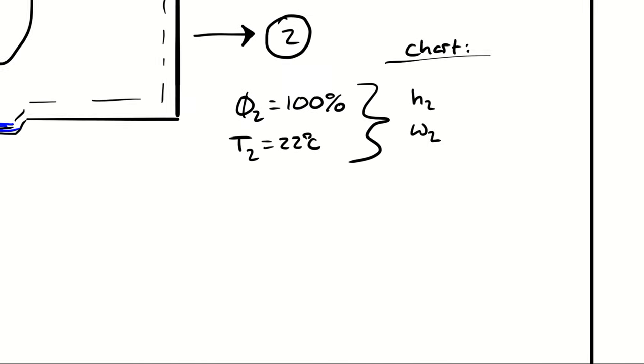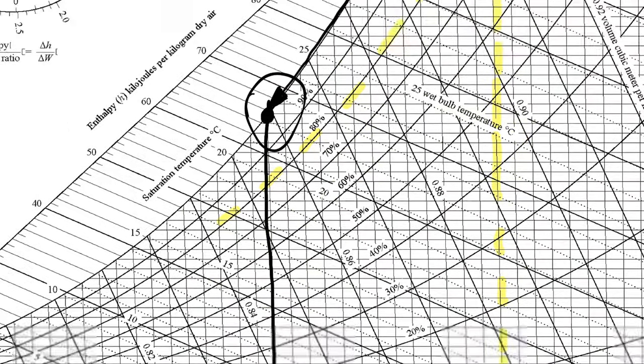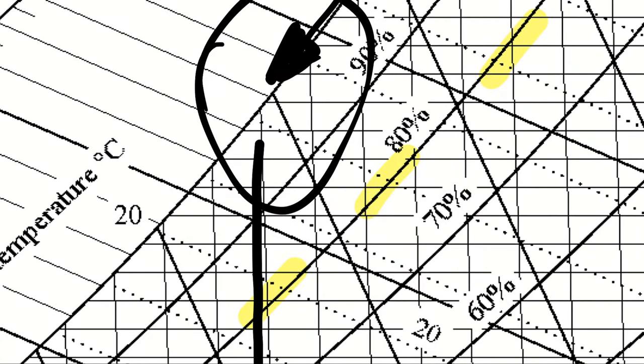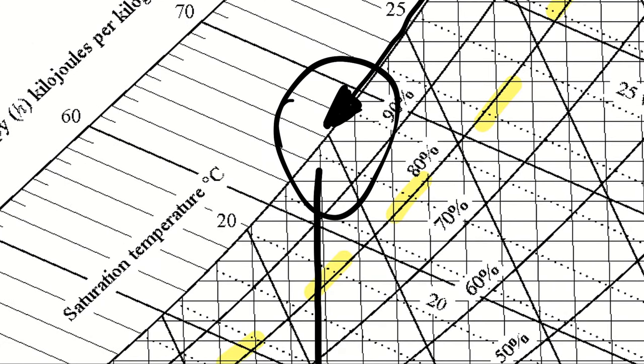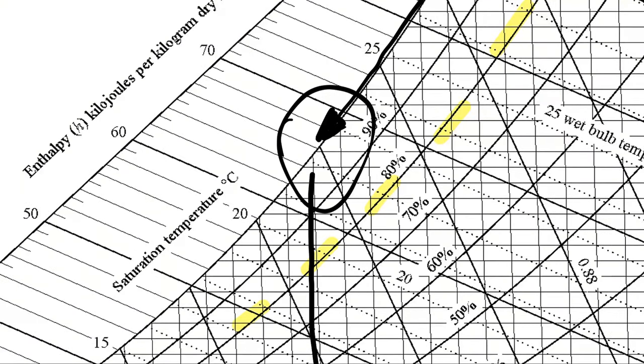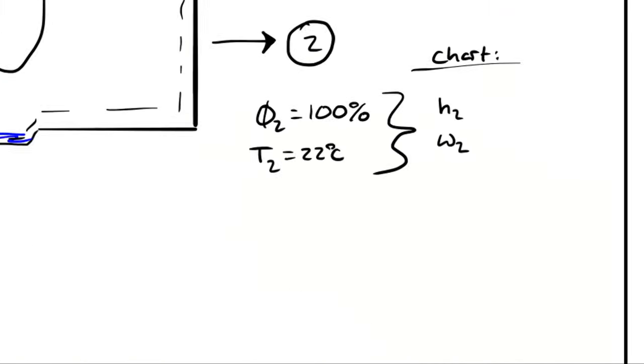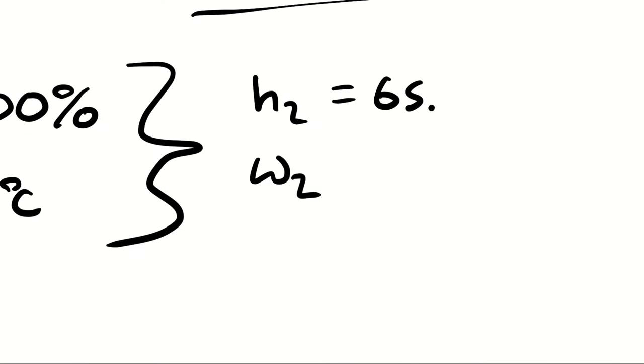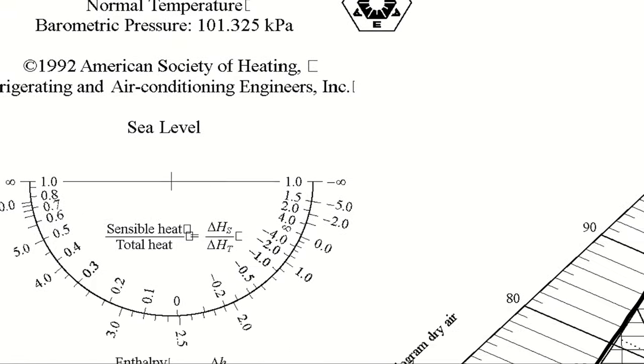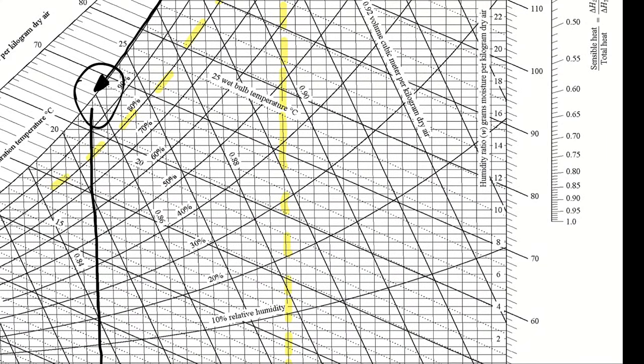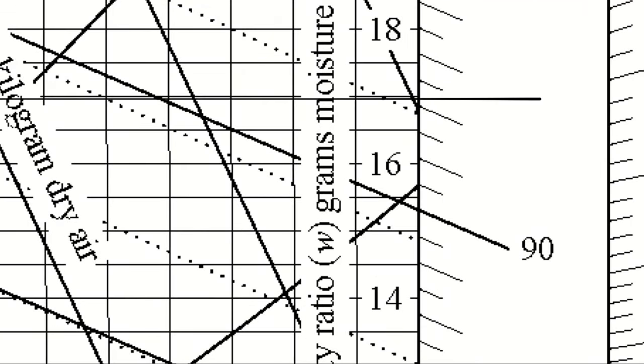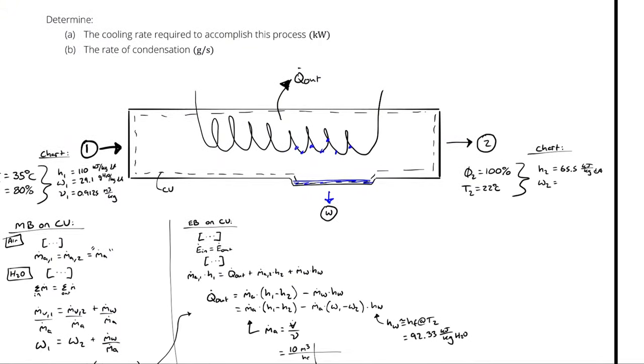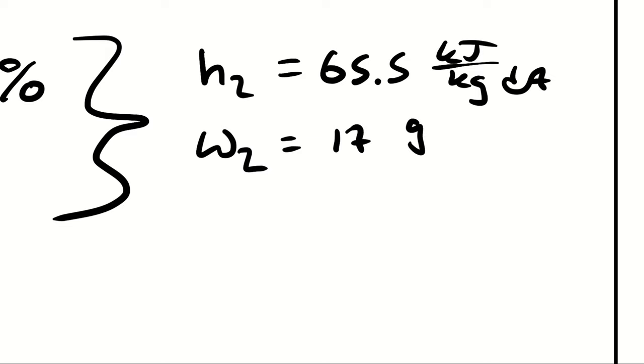At state 2, relative humidity is 100% and temperature is 22 degrees Celsius. From the chart, h₂ is about 65.5 kJ/kg of dry air, and ω₂ is essentially 17 grams of water per kilogram of dry air. Now we have everything we need to finish the question.